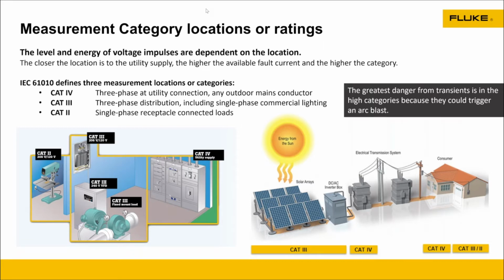Now I like to throw this in because solar is really taking off. Renewable energies are a conversation globally everybody is having. If you're working out in the solar field and working on their arrays, those are considered a category 3 environment. It's a fixed system. It's going through your inverter. Once we go through the inverter and even get into a step-up transformer, we're back out on the grid. So we're back into that category 4 environment. Once we've gone through that and go back into the house, we've now gone back to our category 3 and category 2. The reason why I say this is just know your category environments. It's really critical when we start talking about which meter should I use, appropriate for the job.